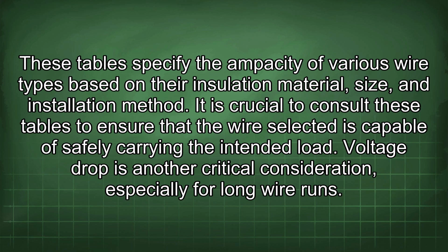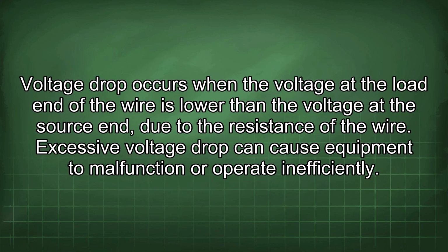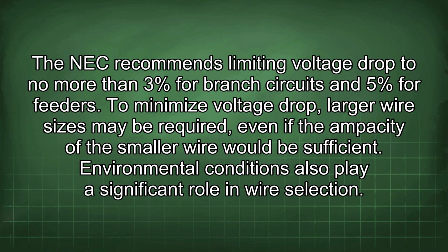Voltage drop is another critical consideration, especially for long wire runs. Voltage drop occurs when the voltage at the load end of the wire is lower than the voltage at the source end due to the resistance of the wire. Excessive voltage drop can cause equipment to malfunction or operate inefficiently. The NEC recommends limiting voltage drop to no more than 3% for branch circuits and 5% for feeders. To minimize voltage drop, larger wire sizes may be required, even if the ampacity of the smaller wire would be sufficient.